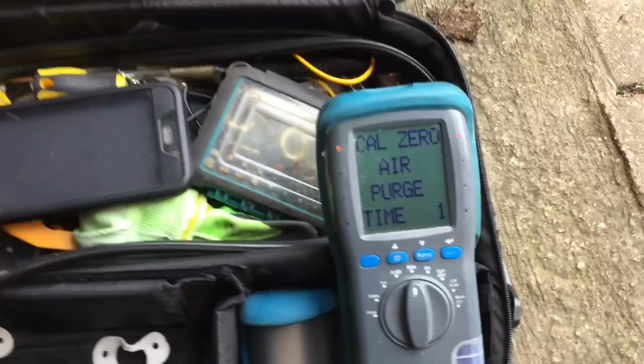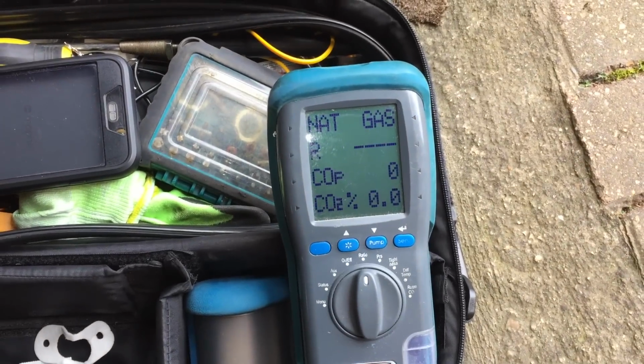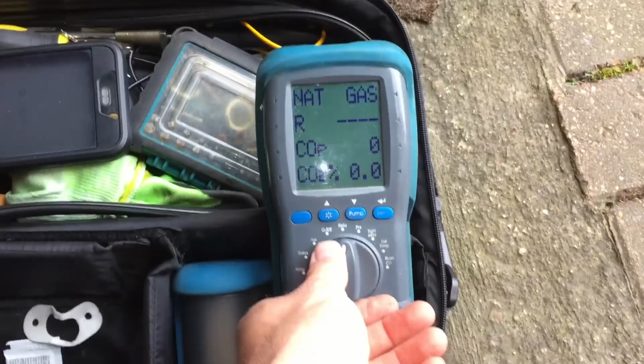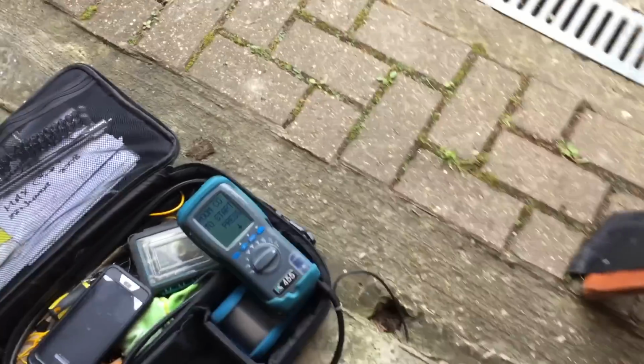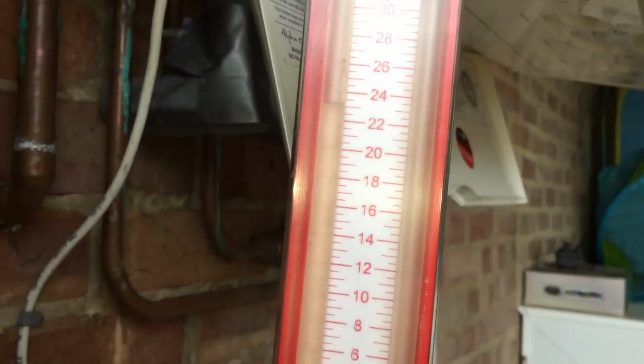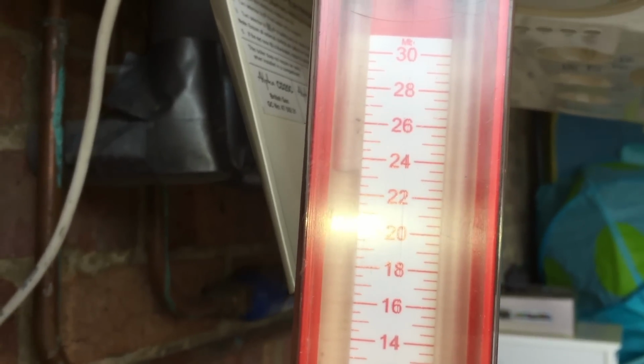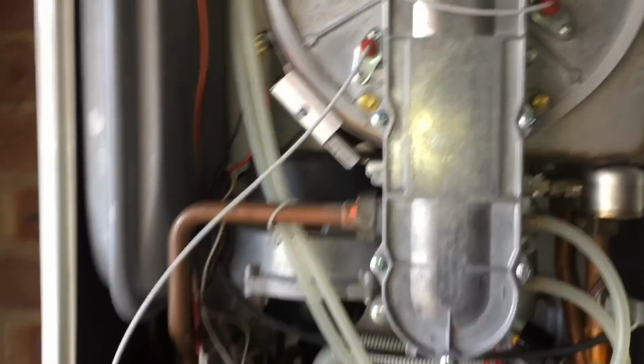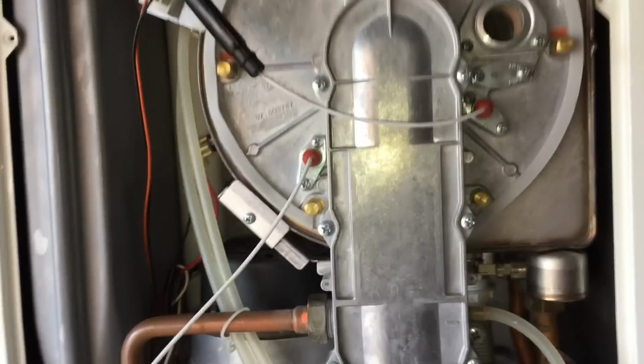Because I can tell it's a poor flame picture, I've got my analyzer set up. I'll leave this here on room CO for a sec so it's not wasting the battery too much, running the pump. And I have my gauge on it, which right now is showing the standing pressure of 23 millibar. But because I know it's a combustion issue, or it appears to be, this is one issue I found so far. First things to check is the gas pressures and the combustion ratios.